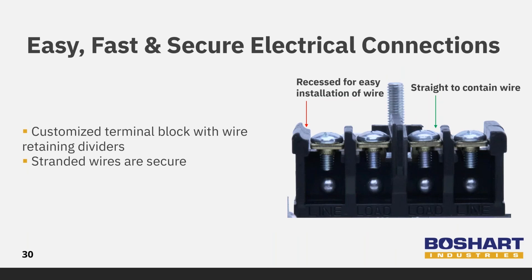Boshart has terminal block dividers which retain the wire under the screw head on the right hand side of each terminal screw. The divider helps stranded wires remain secure under the screw head when the screw is tightened and ensures a good electrical connection. Contractors like this feature because it saves time. Solid conductors can be stripped and inserted under the right hand side without having to bend the wire into a u-shape to wrap around the terminal screw. Simply insert and tighten without having the wire pop out.